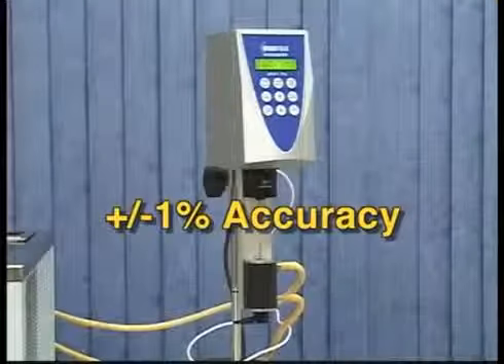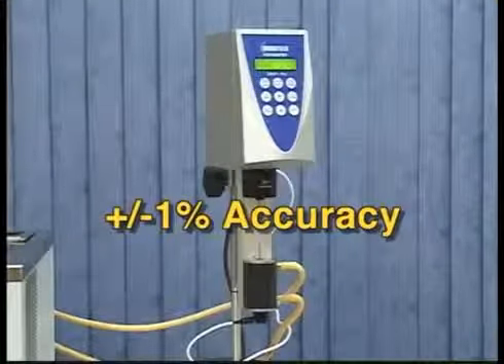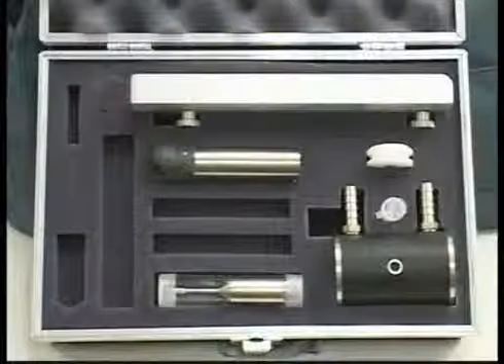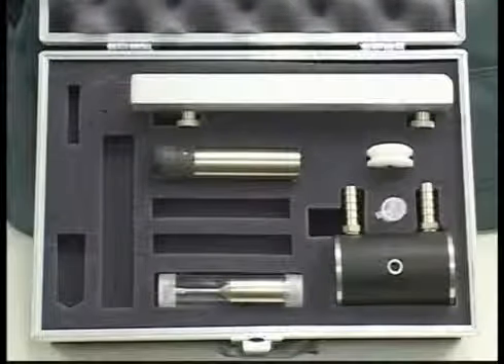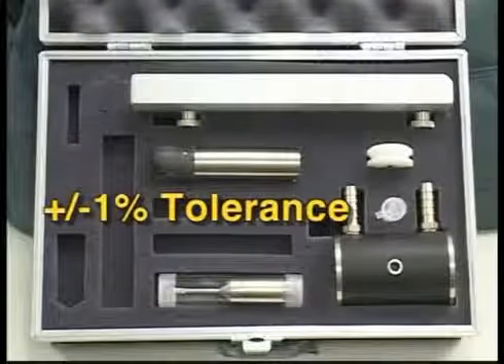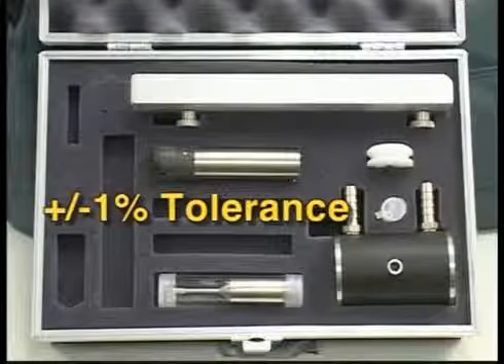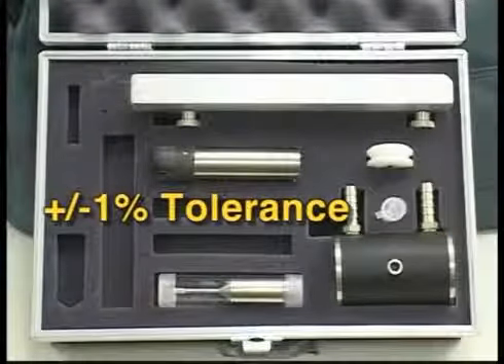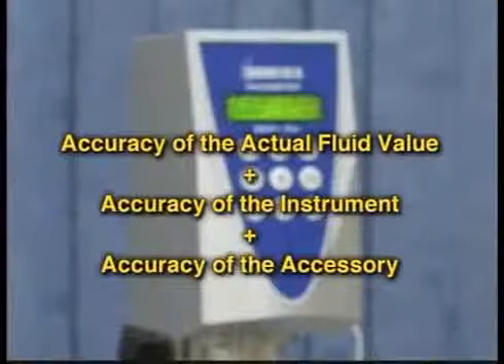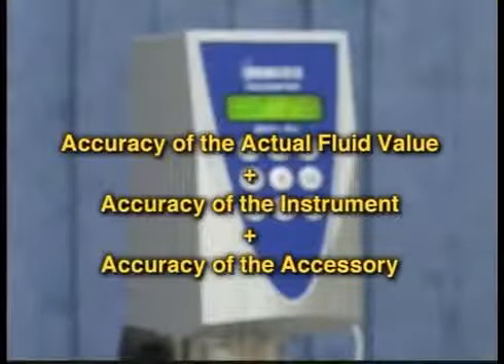Brookfield viscometers have a plus or minus 1% accuracy, but using an accessory like a small sample adapter, an additional plus or minus 1% tolerance for each full scale range is added. The tolerance for your reading is the accuracy of the actual value of the fluid added together with the accuracy of the instrument and the accuracy of the accessory, in this case the small sample adapter.